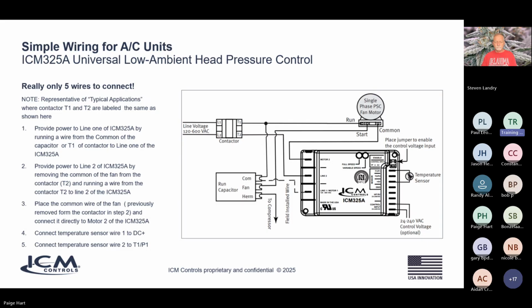So you've got a contactor that turns on your fan motor. That contactor supplies voltage, 240 volts, let's say, to your fan motor. What you've got to do is supply that same voltage to the ICM at line 1 and line 2. And then simply, we're going to break that line 2 that would have gone back to your motor. We're going to break that through the control at line 2 to motor 2. So just like your dimmer switch in your house has power going into the switch, then power coming out of the switch and going to your light bulb, it's very much the same here. Power is coming into the contactor, going out of the contactor through the ICM, which is like your dimmer switch, out to the motor, which is like your light bulb. And all we're doing is breaking one leg of that power through the ICM so we can control the voltage going to the motor.